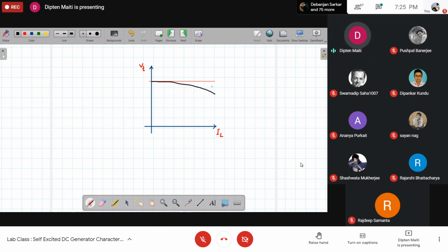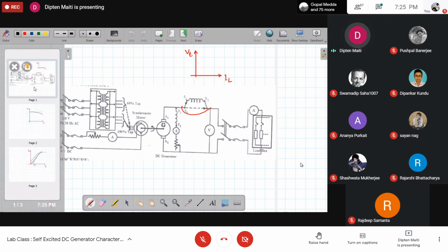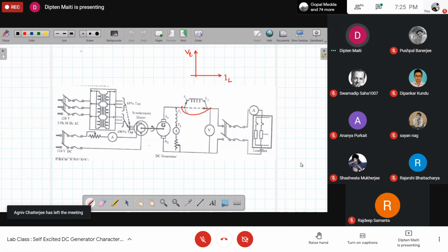So you can actually gradually or slowly short a shunt generator. That would not create a problem. However, you should not short a shunt generator very fast, or not without giving the transient time required for the field to gain its strength, without hampering the armature. Okay.